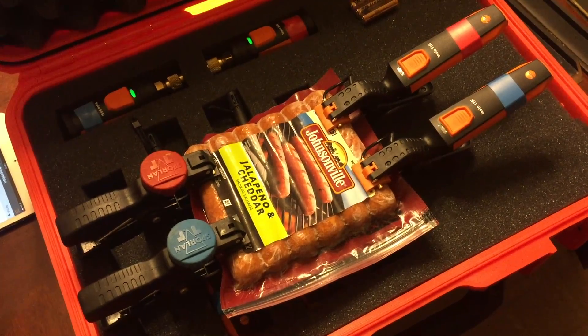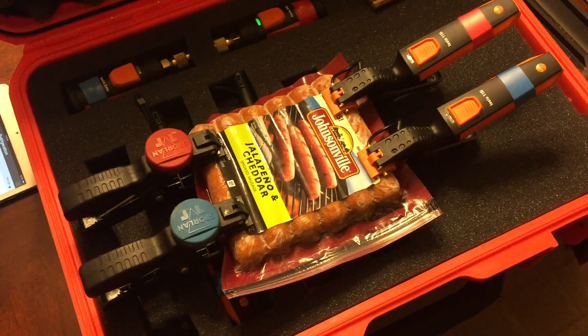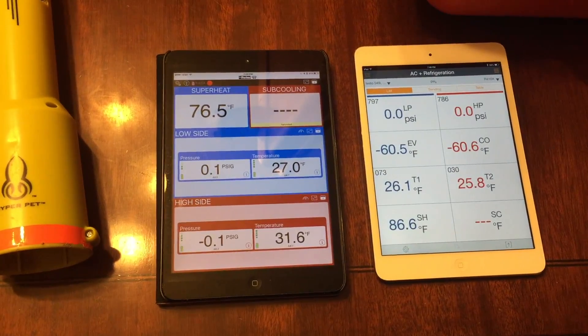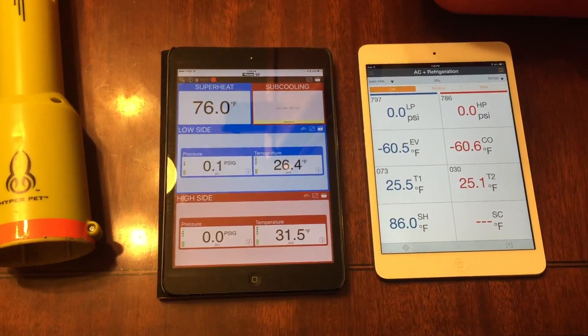I wanted to do a little bit of a calibration test. We've got both the Testo and the Sporlan on a pack of jalapeno and cheddar Johnsonville Brats fresh out of the freezer. Both are on a first-generation iPad with a fresh download of the Sporlan and the Testo app, and no adjustment of temperature at this point simply because we're trying to calibrate. The Testos are both reading about 25 degrees, which to me would be our accurate temperature. One of the Sporlins is reading 26, which is pretty close, and the other Sporlan could stand to have a little bit of calibration.